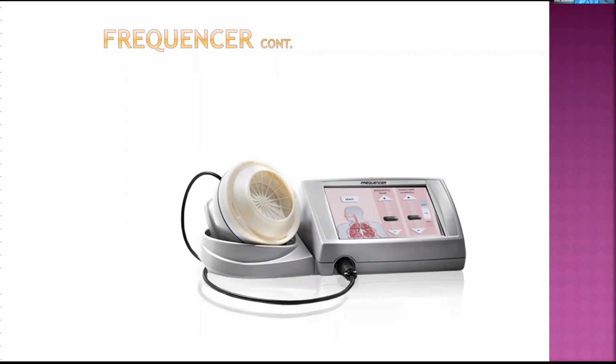The transducer has a filter that goes on it. The filter is there to protect the patient and the machine from bacteria and other bodily issues. But the filter also has a material in it that is designed to not block or impede the sound going through it. The usage is simple.